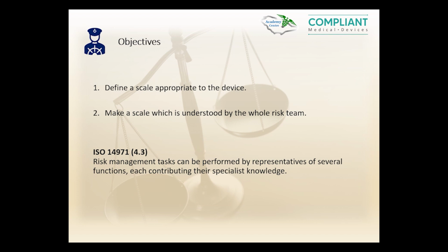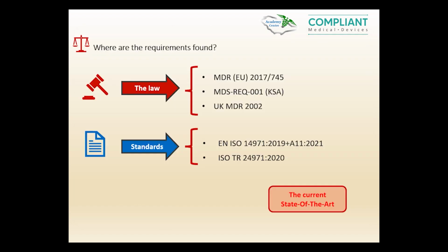The risk team is multidisciplinary, and for most medical devices the risk team is likely to comprise at least one person from design, production, quality, regulatory and clinical, and it's quite possible that we will have other functions serving as well, such as installation, servicing, post-market surveillance. For the duration of the risk analysis, we want them all to be speaking the same risk language.